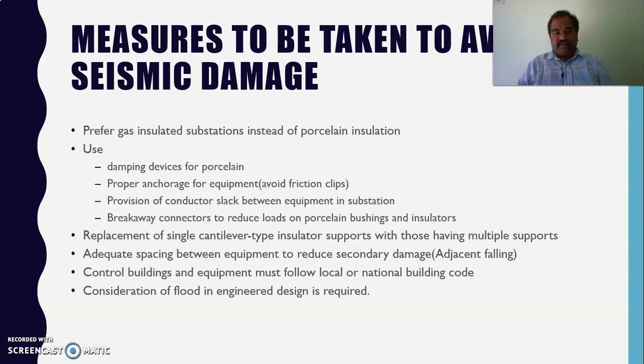Or else you can use damping devices for porcelain, and take care of proper anchorage of the equipment. You are supposed to avoid friction clips, provide conductor slack between equipment in the substation, and always have breakaway connectors to reduce loads on porcelain bushings and insulators. You are also supposed to maintain adequate space between equipment to reduce secondary damages, because if there is damage, the equipment may fall onto the next equipment present there, causing additional damage — this is called secondary damage. So you are supposed to avoid such damages by maintaining space between them.